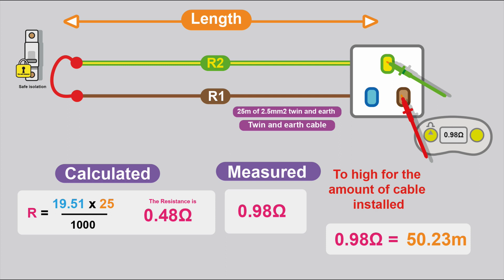Because if you've installed 25 metres of cable, that resistance reading has to be around about 0.48 of an ohm. If you're getting double that, you know there's something wrong. You need to do some further investigation and find out why.